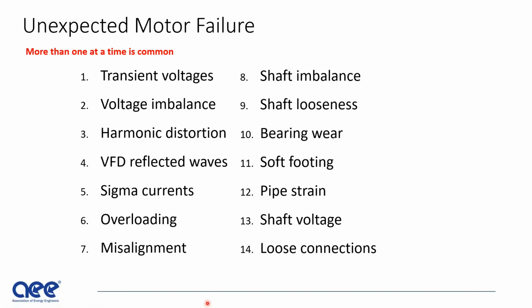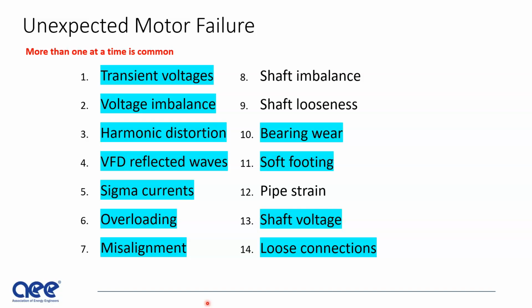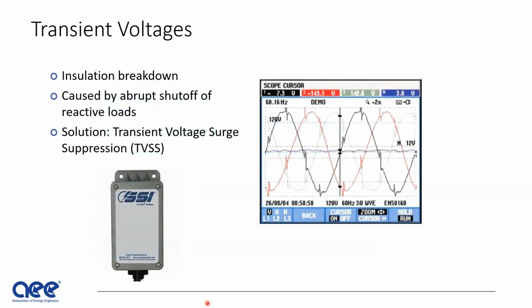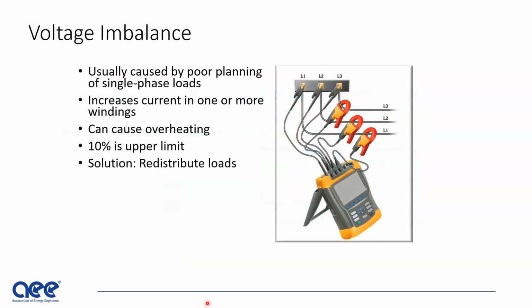Unexpected failures. Here are 14 typical failures that occur in motors. And we are going to cover the ones I've just highlighted very briefly though. So for transient voltages caused by those rapid dV/dt transitions, it's best to use a transient voltage surge suppressor. SSI makes these, that's Surge Suppression Instruments. I've been installing a lot of these lately. Voltage imbalance, it's best to use a power meter and look to see what your balance is on the motor and make sure that you don't exceed 10%.